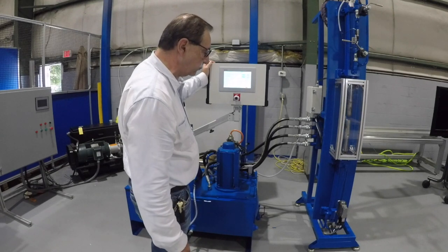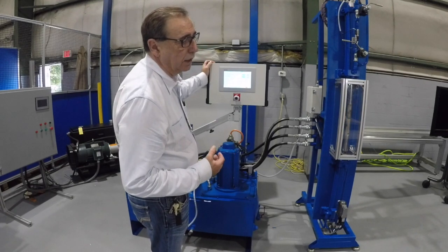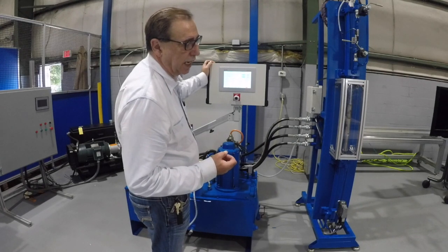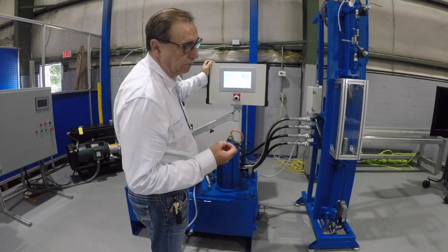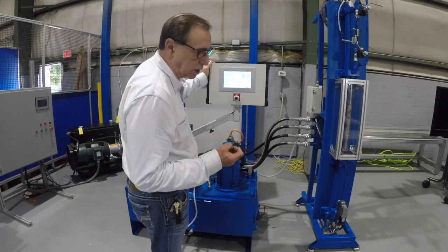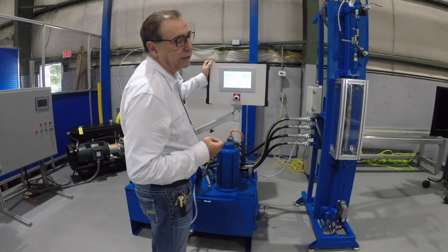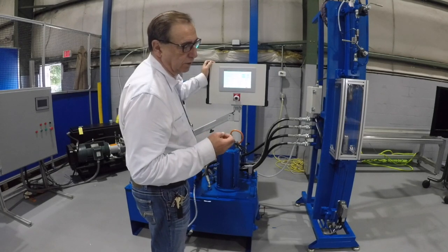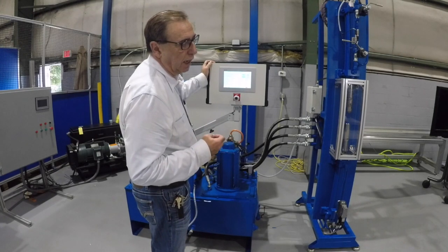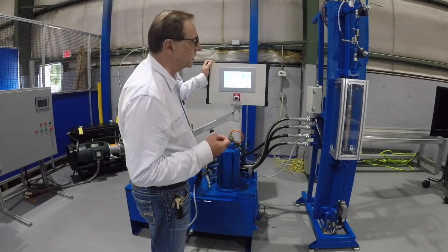We also have, if you need to maintain pressure for a very long time, the ability to use a pressure-compensated pump where we can change the swash plate and require a lot less torque from the servo motor to maintain pressure. But if it's just a short cycle, you could probably do it with just a standard uncompensated piston pump.